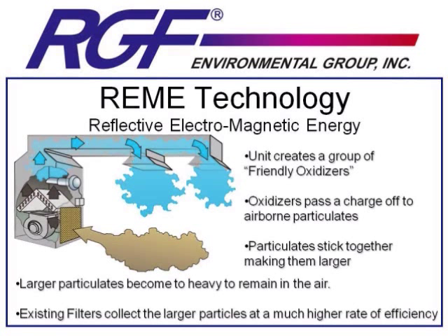By charging the particles — some positive and some negative — they're going to begin to be magnetically attracted to each other. That's going to cause them to stick together and get bigger, or coagulate. These larger particles are now going to be either too heavy to stay in the air and will drop to the ground, or your existing filter system will collect the particles at a much higher rate of efficiency. REME technology doesn't require its own separate filter system; any existing filter system will be better able to collect these larger particles.